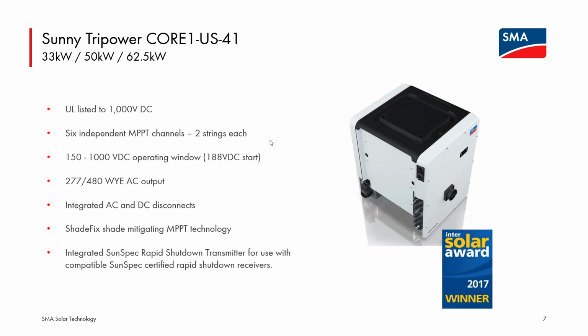Because there are only 2 string inputs for each of the 6 tracking channels that are all independently handled, there is no need for series fusing on the input of the CORE1. So you don't have to worry about 15 amp, 20 amp fuses. Which do I need? How many do I need for installation? How many do I need to stock for service of the device over its lifetime? There is not a need for any series fusing on the input.